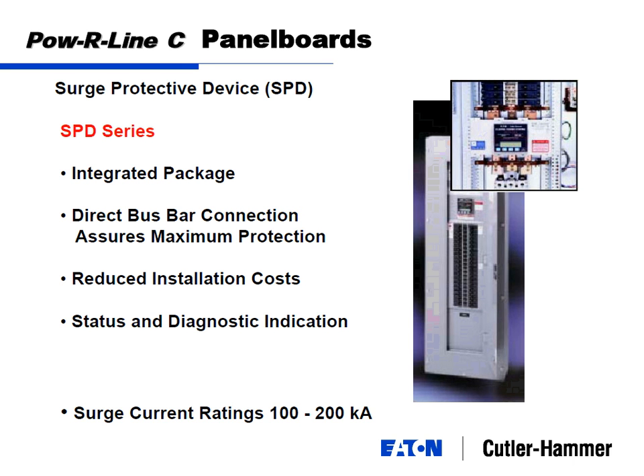So from the inside of the building, things like a Xerox copy machine. I'm sure there's some kind of fax printer or copier somewhere over here. And all these electronics, anything with solid state switching. Every time you switch little solid state resistors and things like that, you send little transient overvoltages across your system. And if you're sending transient overvoltages throughout your distribution system, they go wherever. So if you do something on the other end of this hallway it gets into the electrical system. It could go up to the switchboard, back down to the switchboard, and you could be seeing it in your computers right now.